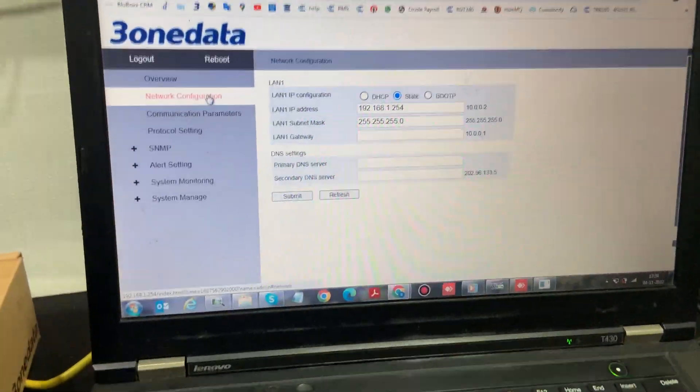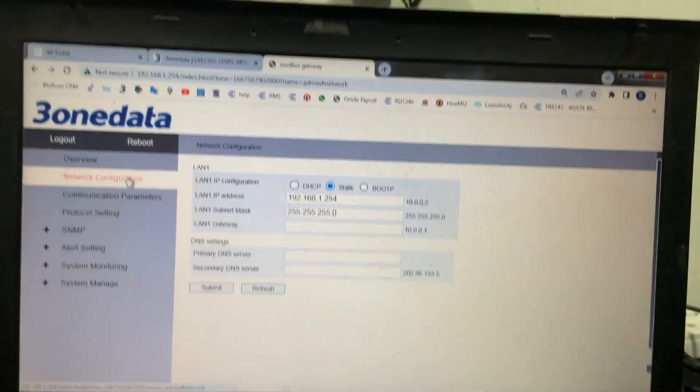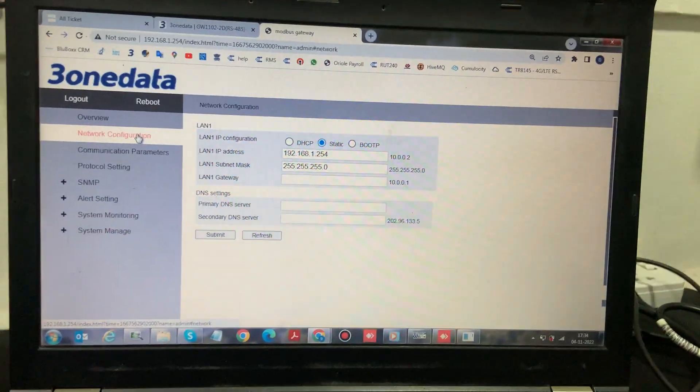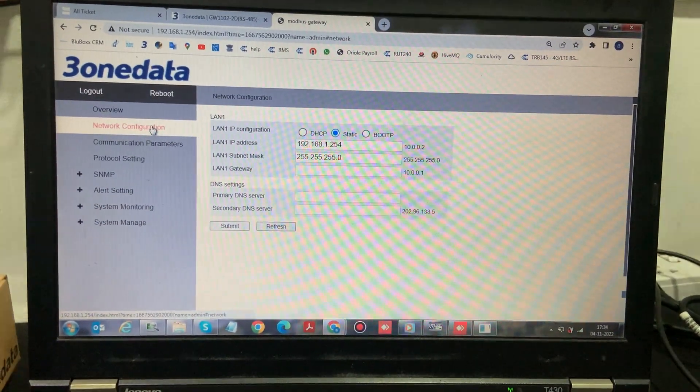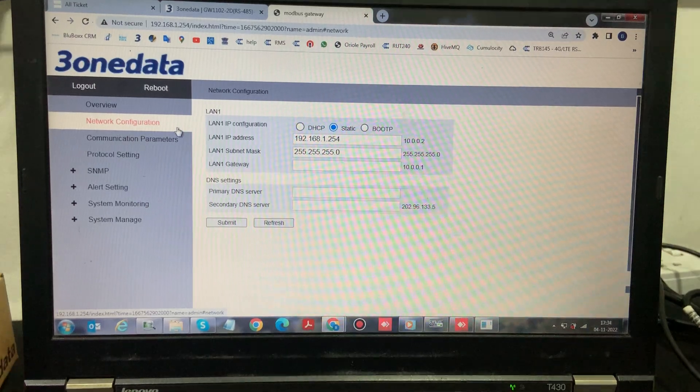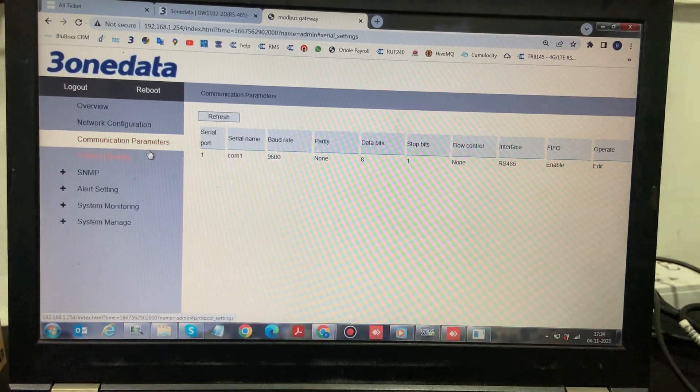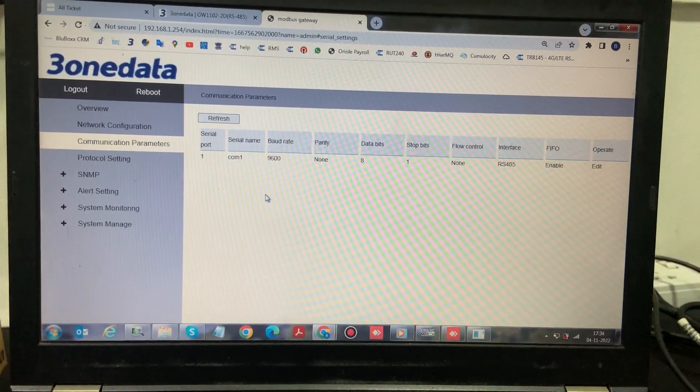So now we have already logged into the device via the web browser. Once you log in, you need to do the following configurations. Go to communication parameters. In this, you need to set the 485 parameters such as the baud rate, parity, data bits, flow control, etc.